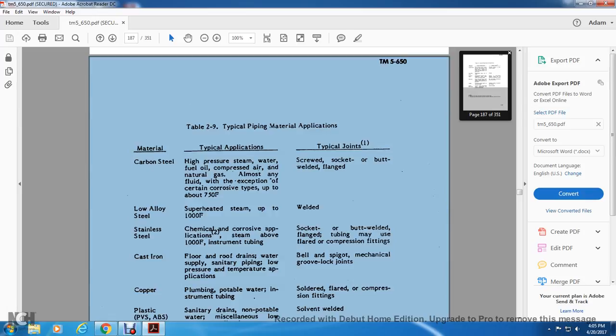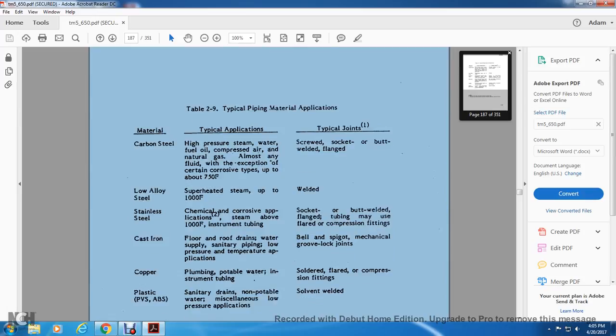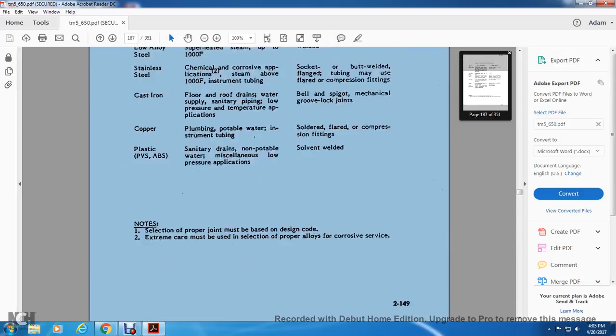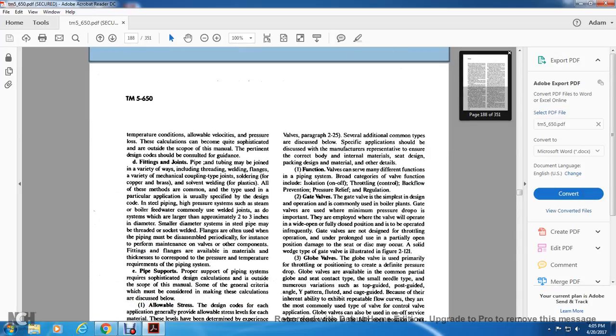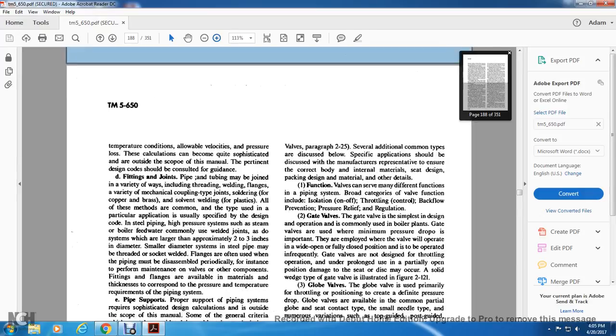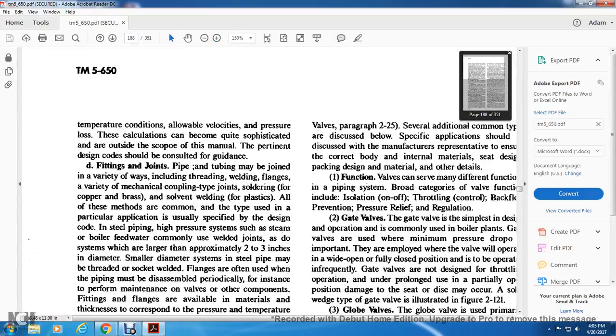Typical piping material applications: carbon steel, low alloy steel, stainless steel, cast iron, copper, plastic. Typical joints and fittings. Pipe and tubing are joined in a variety of ways, including threading, welding, flanges, various mechanical couplings, soldering for copper and brass, and solvent welding for plastic. All of these methods are common.